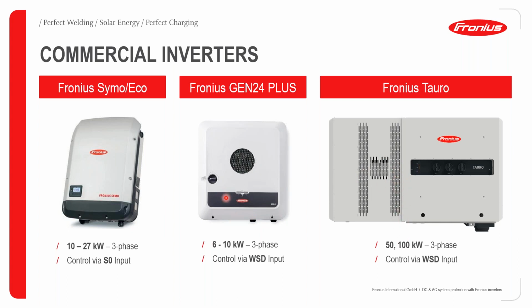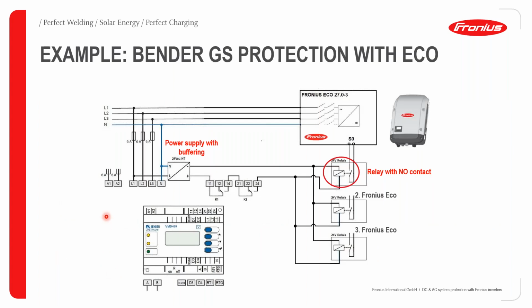So I must mention here that the control for the Gen24 Plus and the Tauro are usually done via the WSD input because of the difference in the data communication interface card. For the Symos, they make use of the data manager, while the Gen24 Plus and the Tauro make use of what we call the pilot. So these will be talked more about in the subsequent slide. So to continue, I will say that the control for the Symos is done via the S0 input.